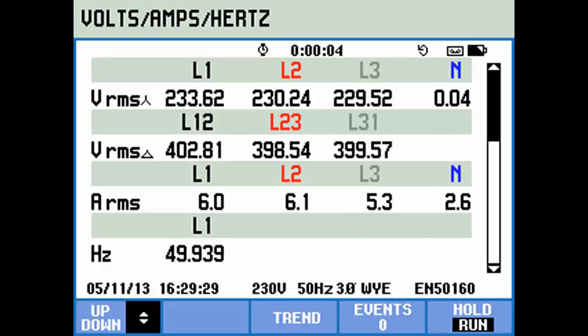We can also show other measurements on the instrument as well using the demo case. Here we see that we have 230 volts of three phase. We have 5 amps or 6 amps of current on the other phases. We can change this current by putting a multiplier into the instrument if we wish, so that we can multiply this by 10 or 100 to get something which looks like a more realistic value.